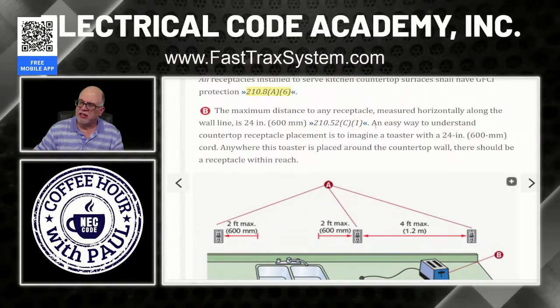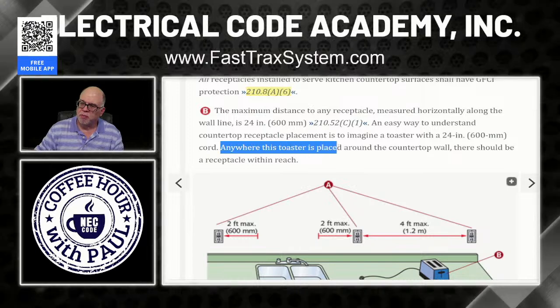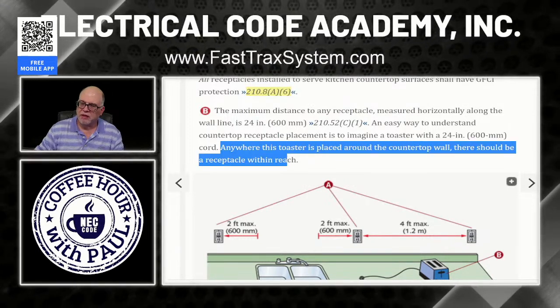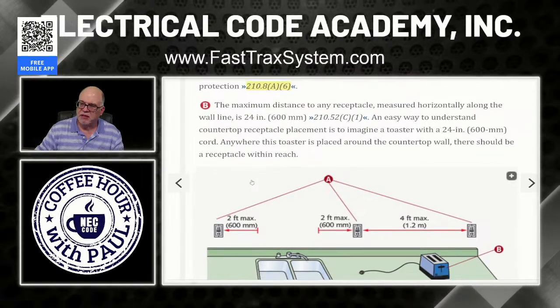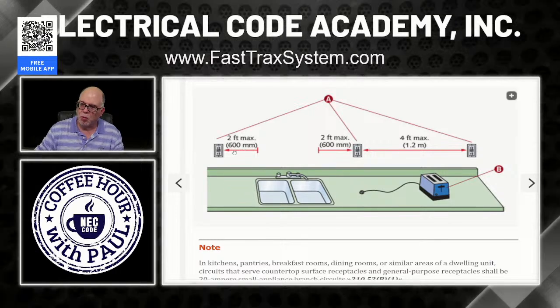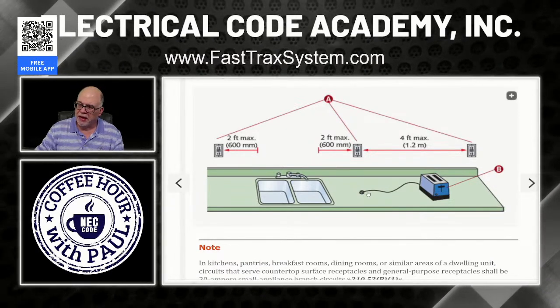All right, now let's look at it this way. The easy way to understand countertop receptacle placement is to imagine that you had a toaster with a 24-inch cord. Anywhere this toaster is placed around this countertop, there should be a receptacle within reach. So what does it say in the code? 210.52(C)(1), it has to be within 2 feet of the edge of the sink. This kind of breaks the countertop. So I have to have one within 2 feet of that. So there it is right there. Could it be at 1 foot? Yes, but the maximum is 2 feet. So this one, max 2 feet.